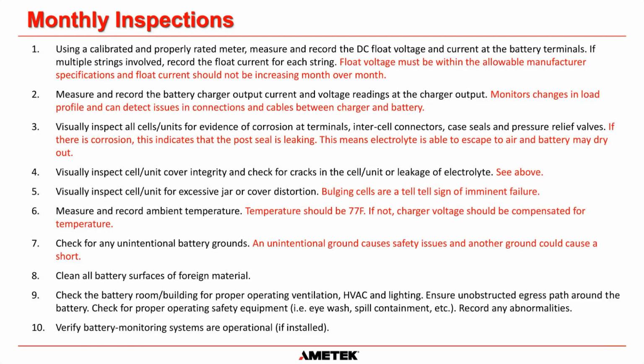But when you get to the battery, you could measure maybe 125 volts because there is a high resistance connection inside the external battery disconnect. So that's why it's important to measure the voltage at the battery terminals and at the charger itself, so you can see if there's any major difference. Okay, now there are going to be some differences in some circumstances because of voltage drop in the cable if it's a long run. But when the batteries are being float charged, there isn't a huge amount of current flowing, so there shouldn't be a huge amount of voltage drop in those cables.